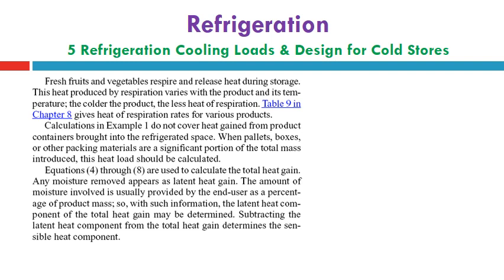Equation 4 through equation 8 are also used to calculate the total heat gain. Any moisture removed appears as a latent heat gain. The amount of moisture involved is usually provided by the end user as a percentage of product mass. So with such information the latent heat component of total heat gain may be determined. Subtracting the latent heat component from the total heat gain determines the sensible heat component.